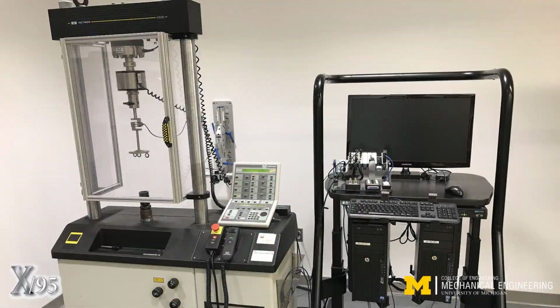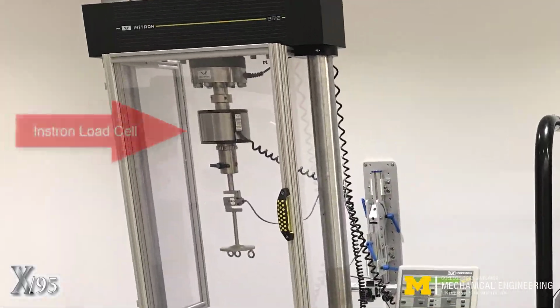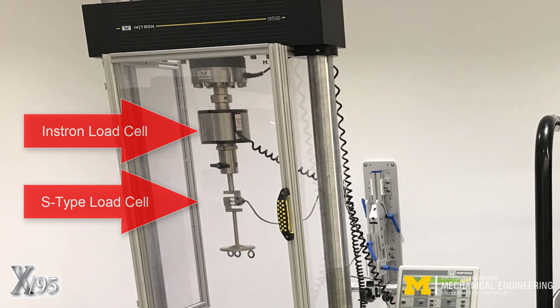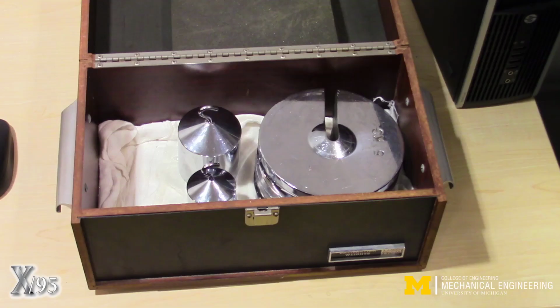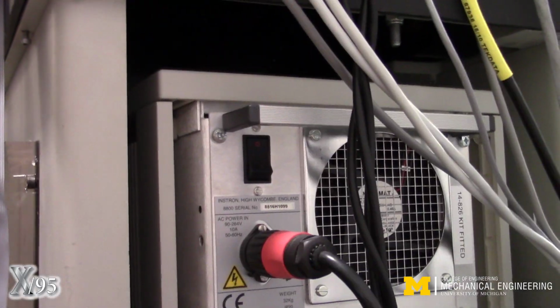In this exercise, you'll calibrate two load cells mounted in series on the Instron 8516. A calibration weight set serves as the standard or reference. The GSI for the first lab section of the day may need to set up the Instron.